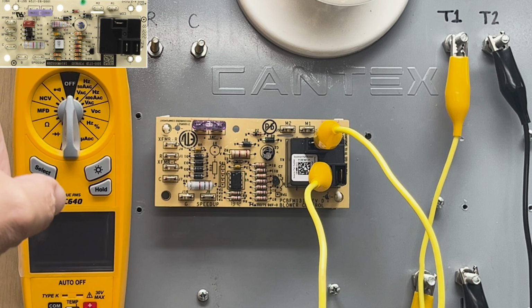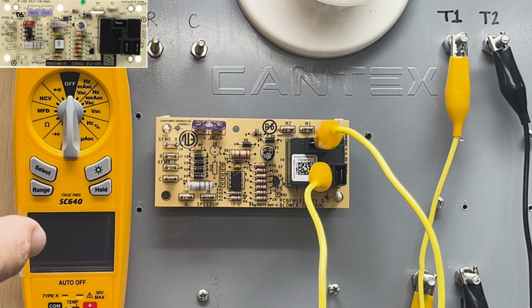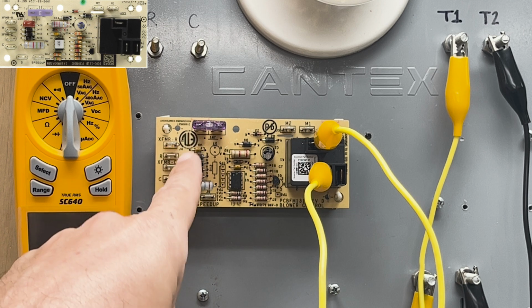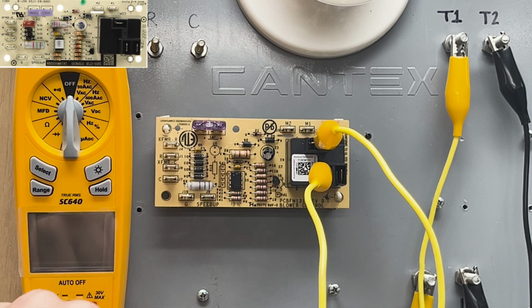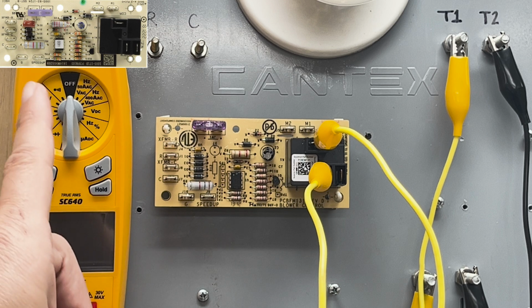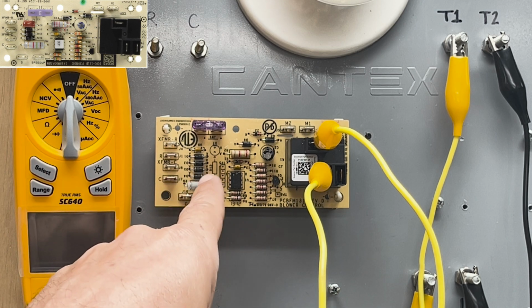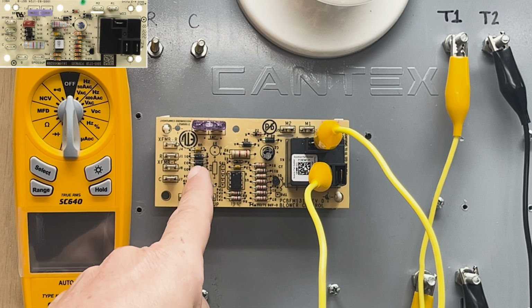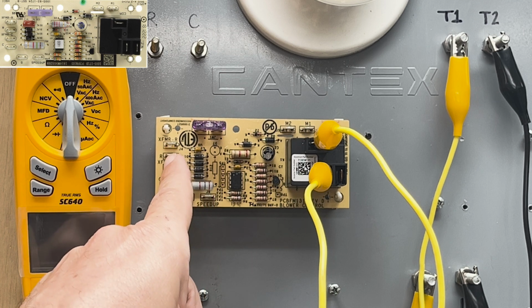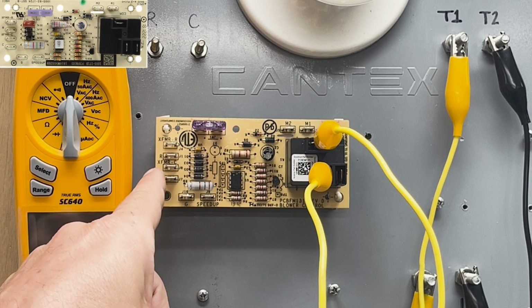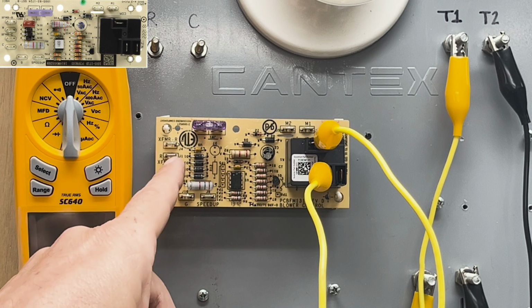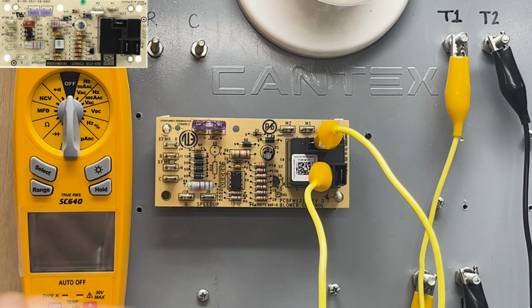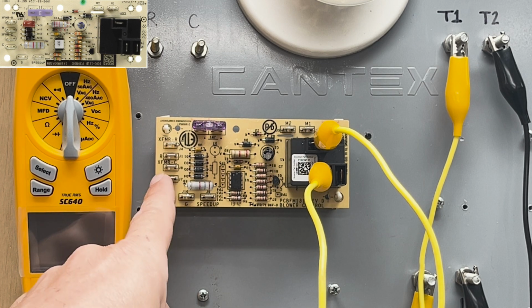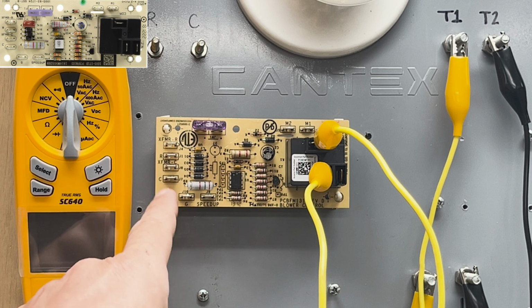If you look up here on the top left, I have a diagram of that so you can follow. J1 is an output, so that R will be an output to the thermostat. Below that we have C, which is common, labeled XFMR-C, so that's transformer. This would be an output path back to the transformer. The C down here will be an input from any other commons I want to use, and as a path through the board, C will go back out to the transformer.